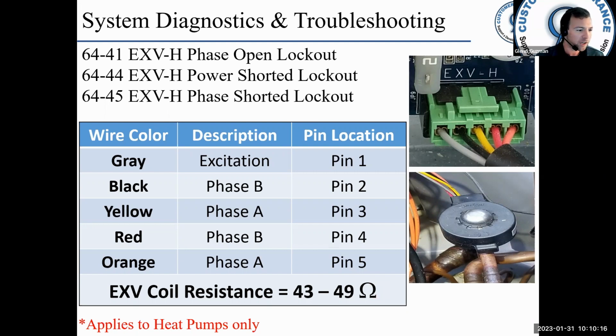6444, the code occurs when the PCM determines the EXV power supply is drawing excessive current. Most likely cause of the fault is the wire attached to pin 1 is shorted to ground. Inspect the wire, harness and plug, and ohm it to ground. Find out if it's actually shorted to ground. Okay, you should have OL if you're ohming to ground.